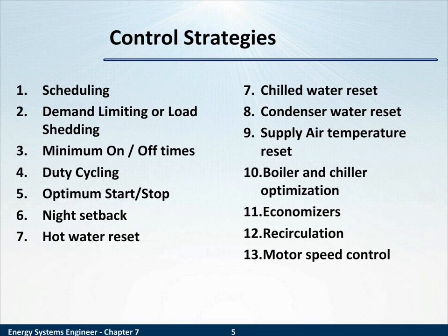The second one is a control system can offer demand limiting or load shedding. The system can reduce your demand by turning something off or turning something down. The control system can coordinate minimum on or off times. Some systems, once on or once off, need to remain in that state either for efficiency or for equipment lifetime for a certain period of time. And then they can be allowed to be switched to the other state, either off or on. Duty cycling means to change or control the ratio of on period to total cycle time of this on and off controlled equipment. So duty cycling changes that ratio.